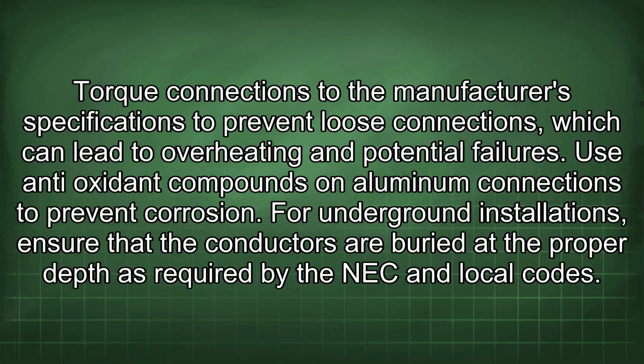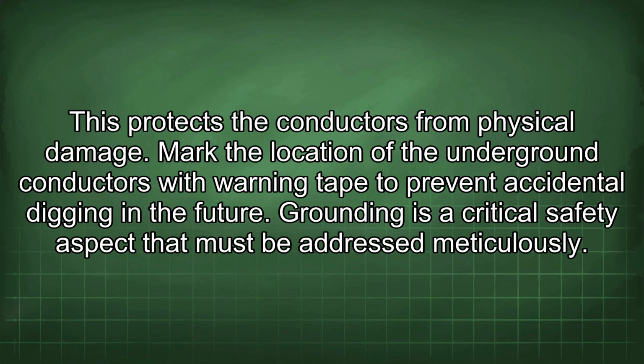For underground installations, ensure that the conductors are buried at the proper depth as required by the NEC and local codes. This protects the conductors from physical damage. Mark the location of the underground conductors with warning tape to prevent accidental digging in the future.